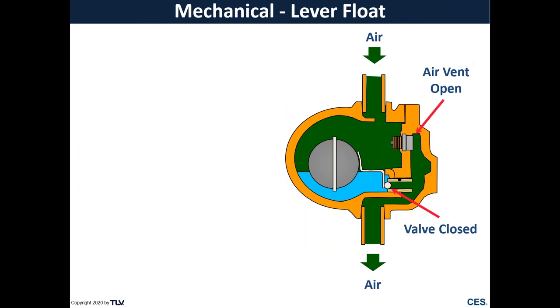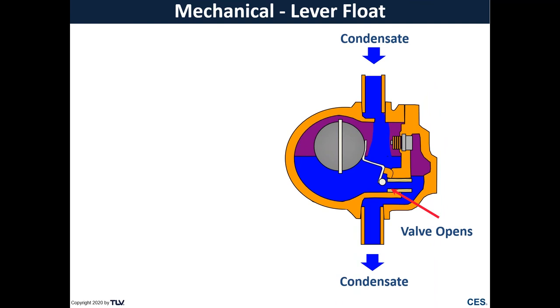The next steam trap I want to cover is a lever float. So this lever float actually has a thermostatic element inside of it. And so during startup, cold condensate and air, that thermostatic element's going to be wide open and it's going to discharge air. As condensate begins to enter the trap, that float's going to become buoyant, opening the lever mechanism, allowing condensate to pass through the main valve seat.